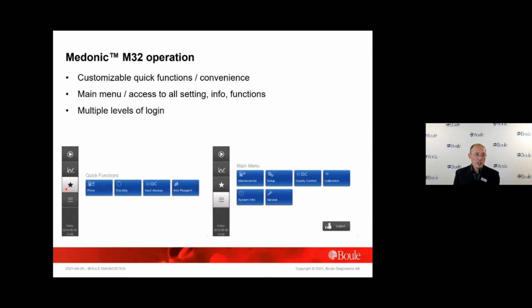Next, in the quick function folder, by default, these functions are often used. Prime cycle is probably the most used function. In case any fluidic system problem appears, the end user is asked to do a prime cycle. Since in some parts of the tubing the liquid is not exchanged between each cycle, in case an air bubble gets into such a tubing segment, only a prime cycle can reset the total fluidic status.